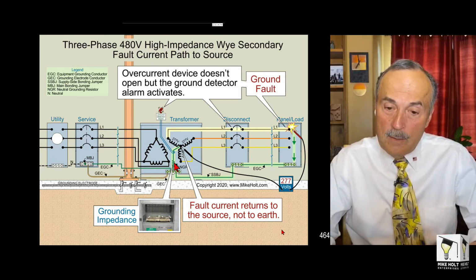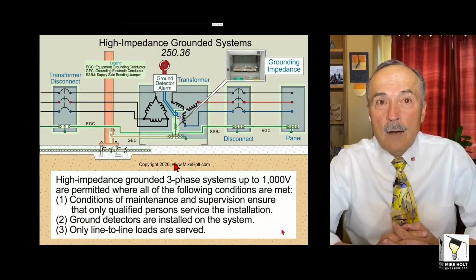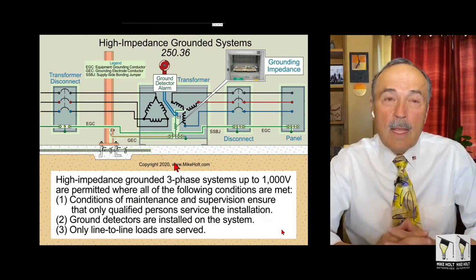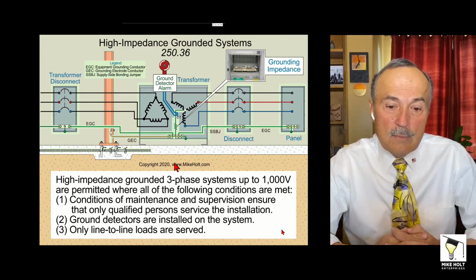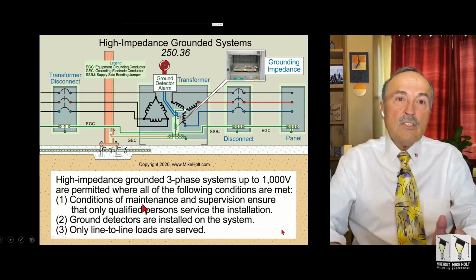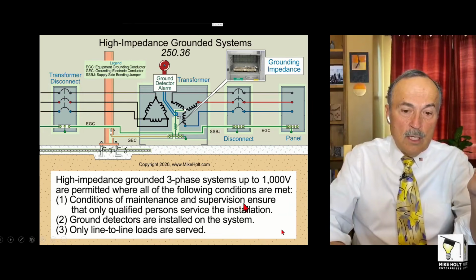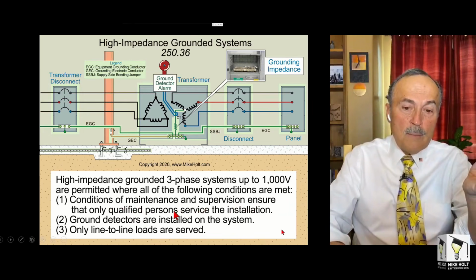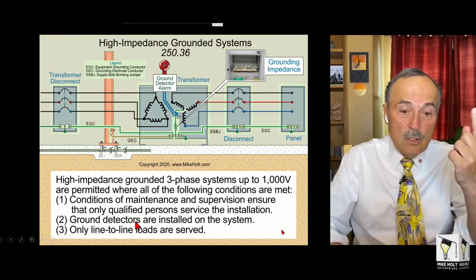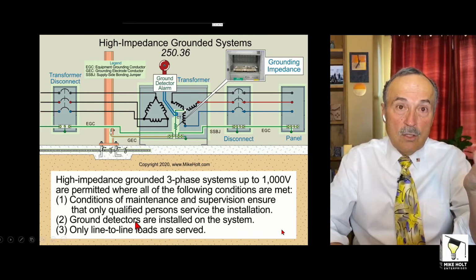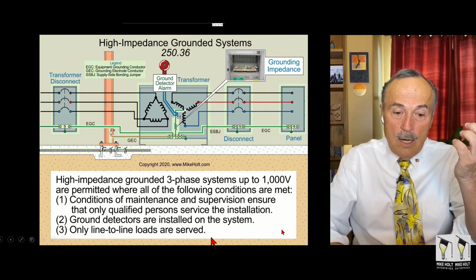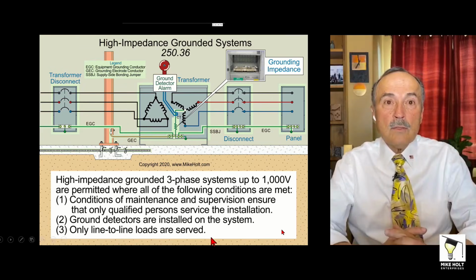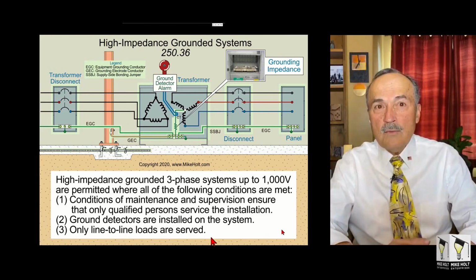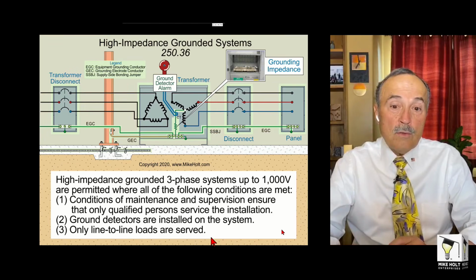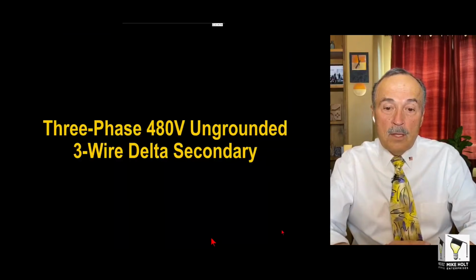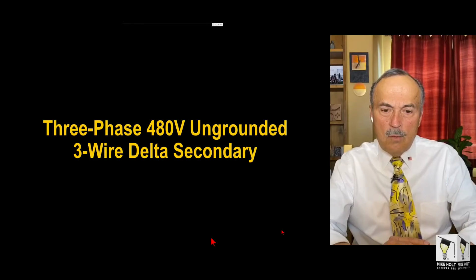The problem with the three-phase, three-wire, high resistive or high impedance grounded system is that you have restrictions. It can only be installed where conditions of maintenance and supervision ensure that qualified persons will service it, number 1. 2, that there are ground detectors installed. And 3, only line-to-line loads are served. So you can only have 480 volt phase to phase, single phase or three-phase. Three-phase ungrounded, 3-wire delta secondary.